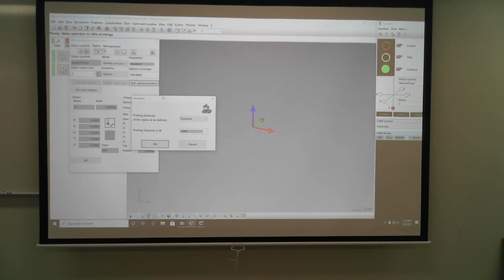We just hit OK. And then it asks you for probing behavior, and all of that is already set to the default as well. If you had a different type of head, like we have VAST XXT. If you had a VAST sensor, you can actually probe a lot faster when you're scanning, so that lets you set that behavior. We only have the VAST XXT, so the defaults are good. All right, now this looks a little different on mine because I'm in simulation and you're on the real machine. On the real machine, it should give you a dialog.